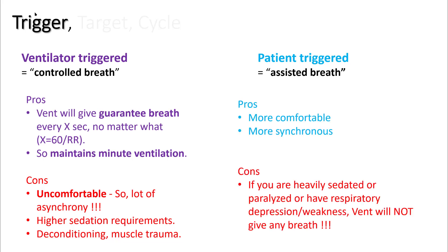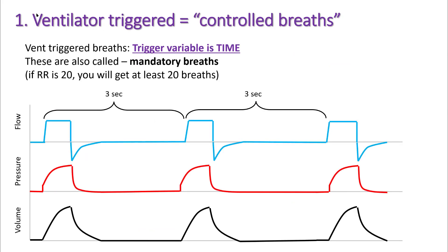Patient-triggered breaths are more comfortable as they are more synchronous with the patient's breathing. However, if your respiratory drive is compromised — for example, if you are heavily sedated, paralyzed, or have muscle weakness — the ventilator will not give you any breath. In ventilator-triggered breaths, the trigger variable is time. If you set your respiratory rate at 20, you will get at least 20 breaths spaced every 3 seconds. These are mandatory breaths.